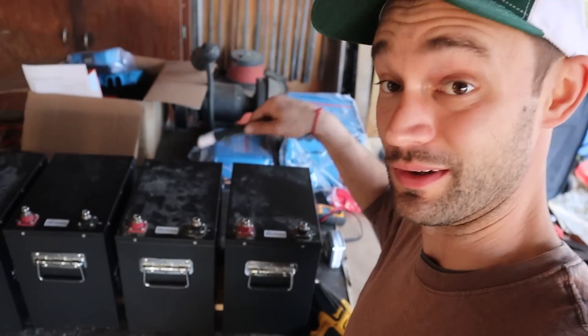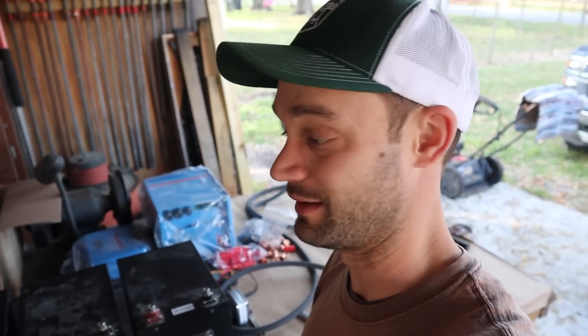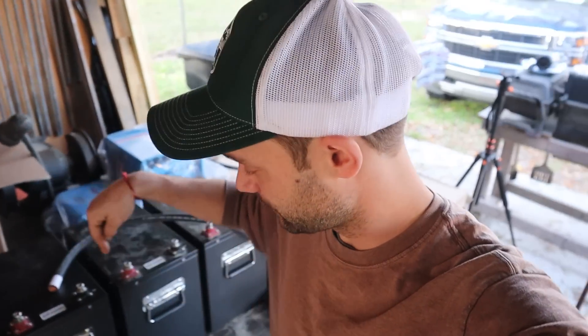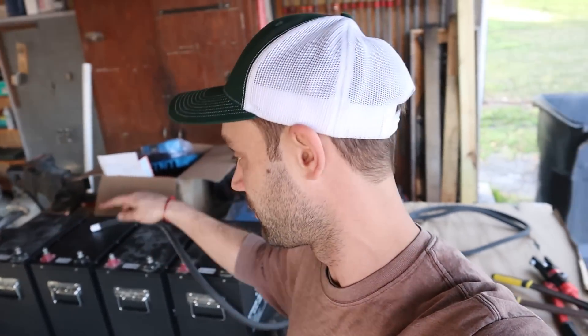All I'm going to be doing is connecting all these down and then putting the charger on them. You've got to make sure your batteries are balanced before you put them in. The number one mistake I see is that people don't balance their lithium batteries together - they end up with an uneven battery bank and deplete those warranty years. I'm going positive to positive, negative to negative all the way through. I need six equal lengths. I want to make sure the wire is equal lengths between terminals so the batteries are balanced as they're discharging and charging. Then I need to measure from the most negative and most positive terminal up into the Lynx distributor - those also want to be the exact same length.